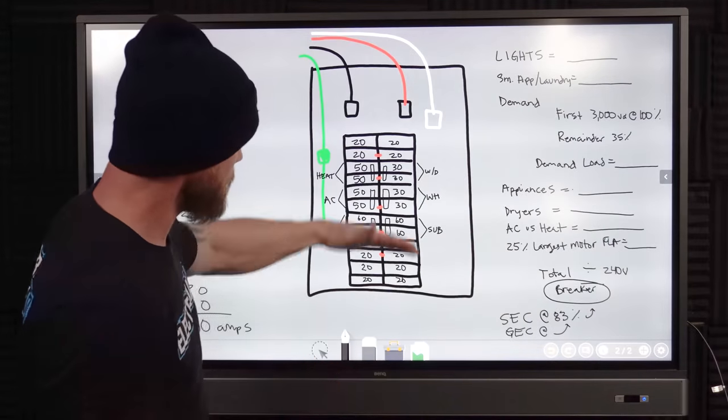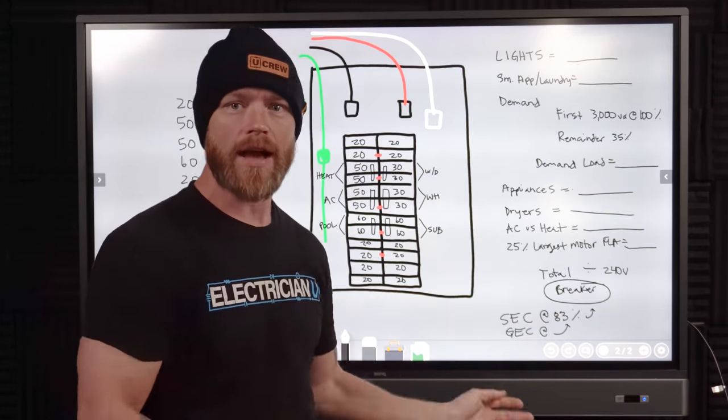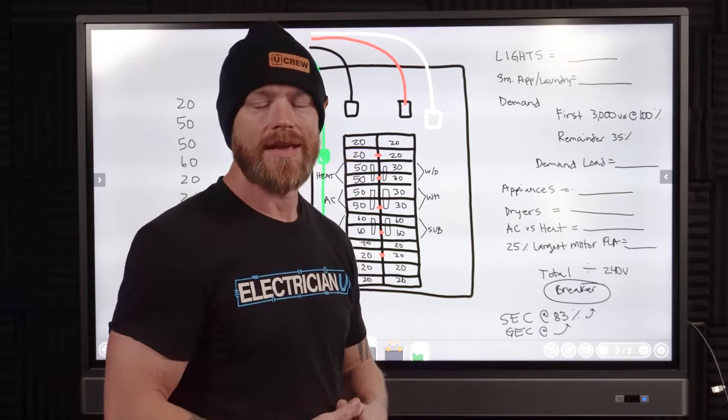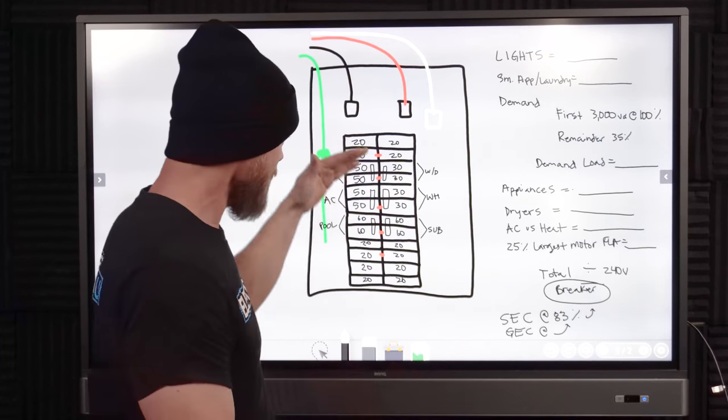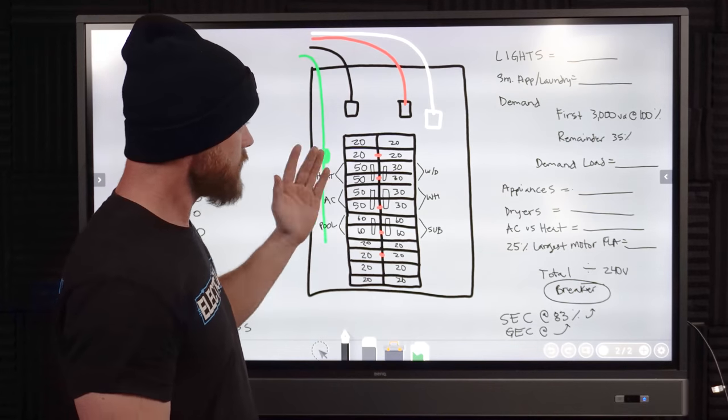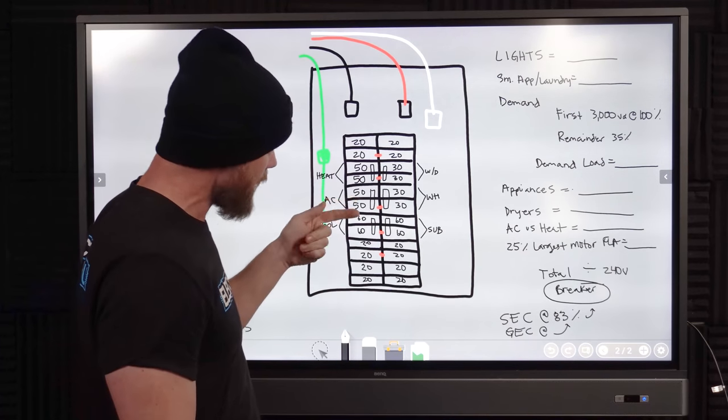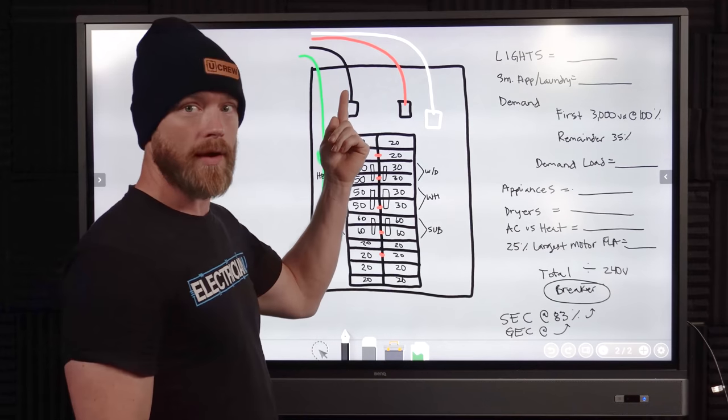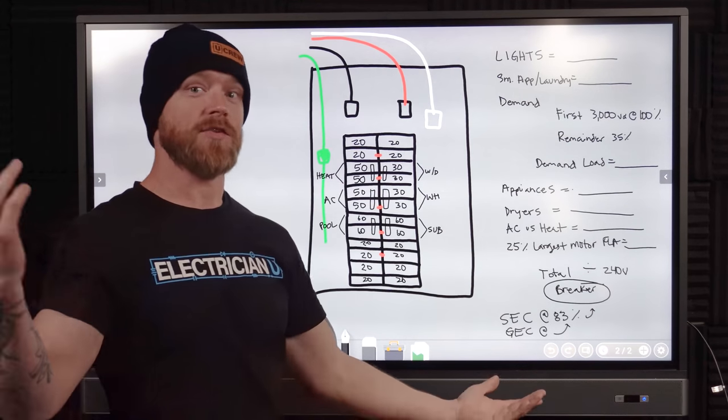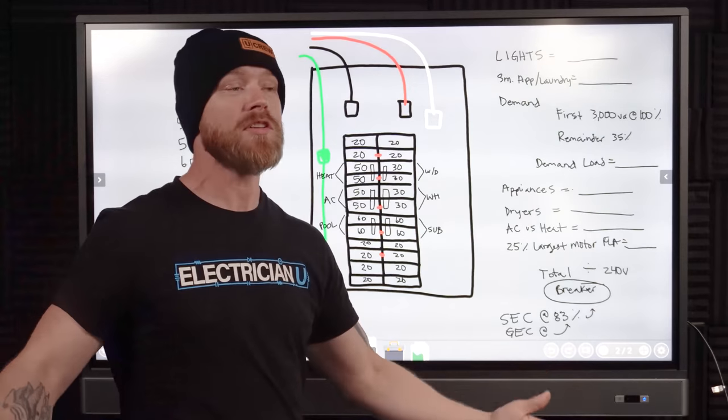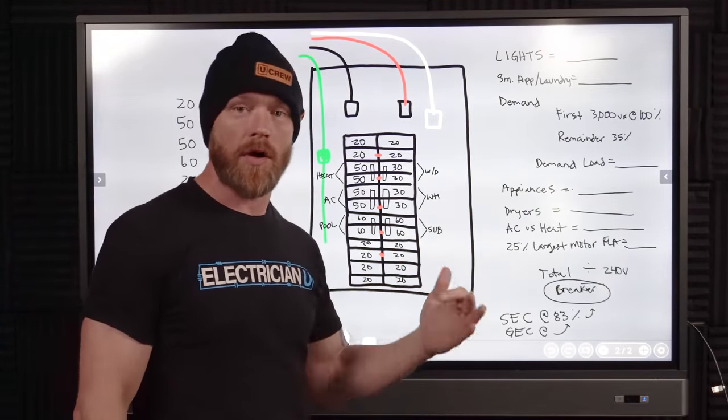Some people think when you see a panel and these are all individual breakers in there, that for some reason you're just supposed to add all of them up and that's the size of the service. And that's not what you do. The reason is it would be so expensive. If you added all of this stuff up, you would get 400 amps on just one of the phases. So if you added every black breaker on black phase alone, you'd have 400 amps. Red phase, you'd have 400 amps. So you definitely wouldn't add every single number in here because then you'd have an 800 amp number and nobody's putting 800 amp services. It's just unnecessary.